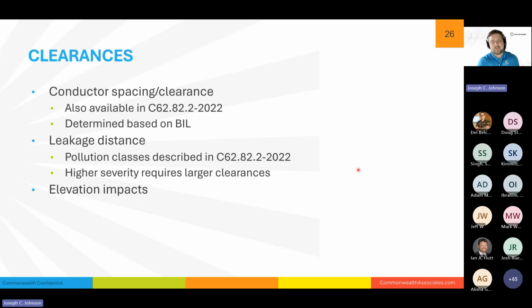They're usually baked in. So a BIL of 900 kV will have a specific amount of spacing and clearance requirements. It's important to adhere to these, of course, because if you violate those, your risk of flashover at those locations is significantly higher because you don't have the benefit of that insulating air.